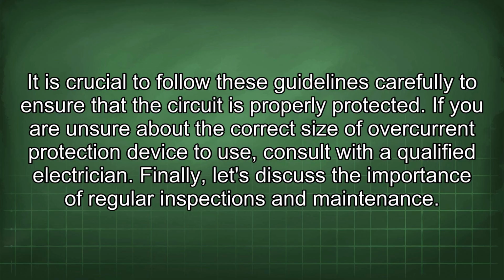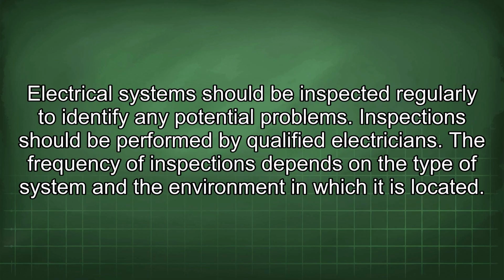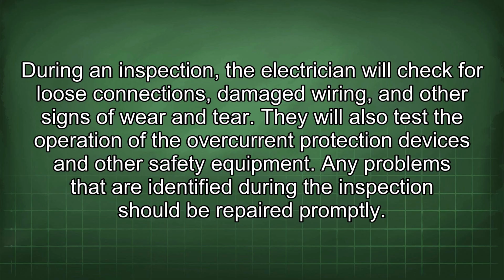Finally, let's discuss the importance of regular inspections and maintenance. Electrical systems should be inspected regularly to identify any potential problems. Inspections should be performed by qualified electricians. The frequency of inspections depends on the type of system and the environment in which it is located. During an inspection, the electrician will check for loose connections, damaged wiring, and other signs of wear and tear. They will also test the operation of the overcurrent protection devices and other safety equipment. Any problems that are identified during the inspection should be repaired promptly.